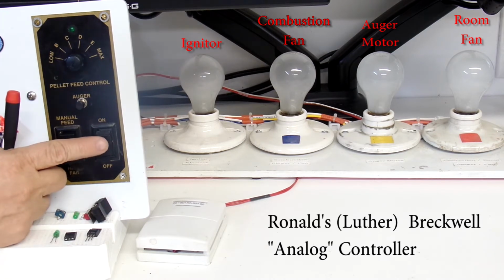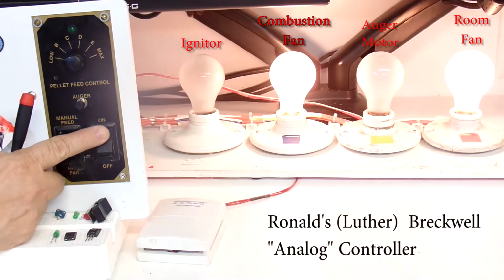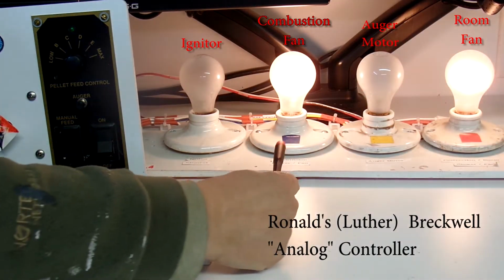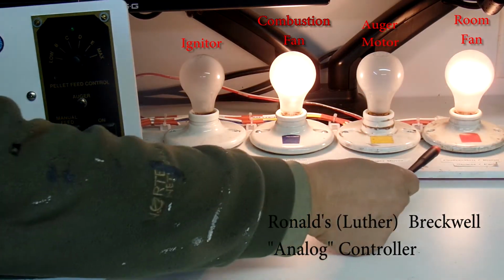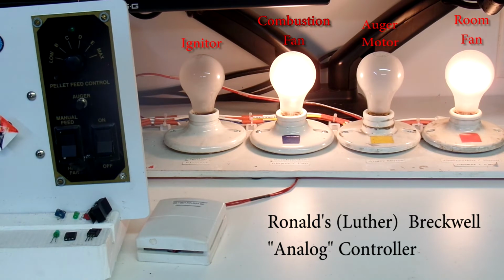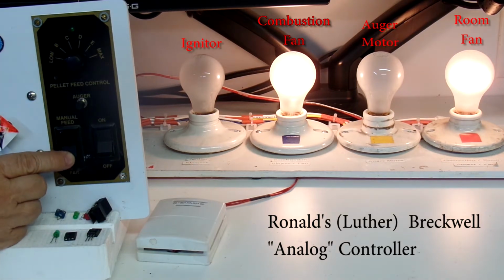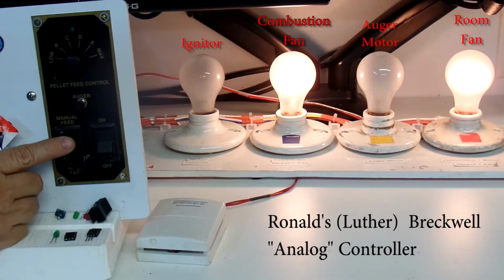So let me go ahead and turn things on, and when I do, a couple lights will come on. There we have it. We have the combustion fan has come on, and we also have the convection or room fan. So I'm in manual mode now because we see that the green light up here is not on. So there's a few things I can check. One, of course, is the fan, which does not make any difference at all. Notice it's on high all the time.